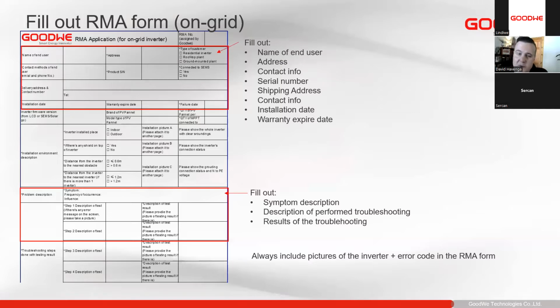One thing that's always important with almost all of our RMA forms is to include a few pictures. So the picture of the installation. If you do go on site, please take a picture of the installation as well as a grounding measurement to make sure that the inverter is properly grounded. For the grounding measurement, we don't want to see the grounding measurement in the distribution board. We want to see the grounding of the inverter itself, from the inverter casing to the grounding system. So you'll see in the RMA form that will always be there.